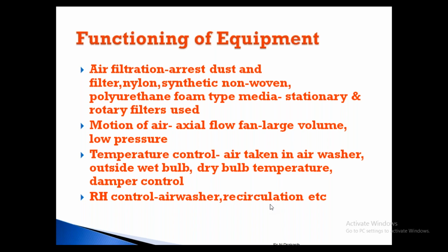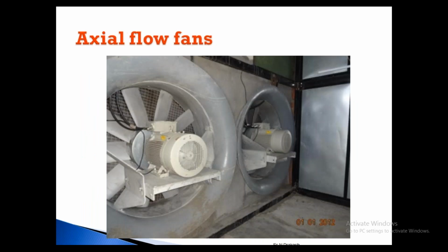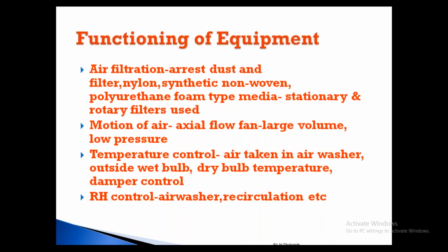Nylon filters are used. In some places synthetic non-woven is used. Polyurethane foam media is used. Acrylic fibre material is used. And you have different types of filters, stationary and rotary. The advantage of the rotary filter is uniform condition. It is always being cleaned, so there is no inequality in the dust level in the production hall. Whereas stationary means the air just comes and hits the stationary filters, and somebody has to clean them manually. That delay will create problems.